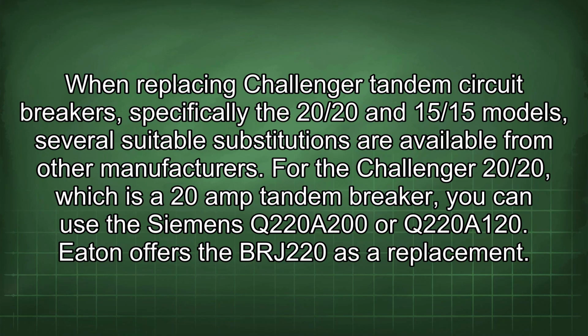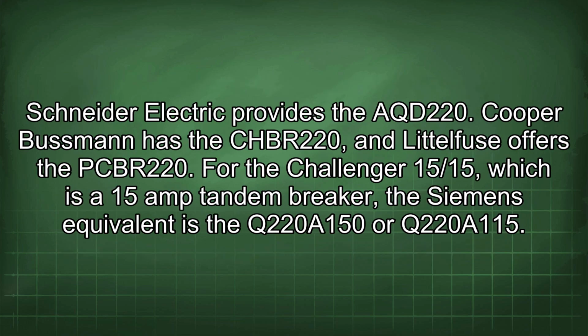When replacing Challenger tandem circuit breakers, specifically the 20/20 and 15/15 models, several suitable substitutions are available from other manufacturers. For the Challenger 20/20, which is a 20 amp tandem breaker, you can use the Siemens Q220A200 or Q220A120. Eaton offers the BRJ220 as a replacement. Schneider Electric provides the AQD220. Bussmann has the CHBR220, and Littelfuse offers the PCBR220.